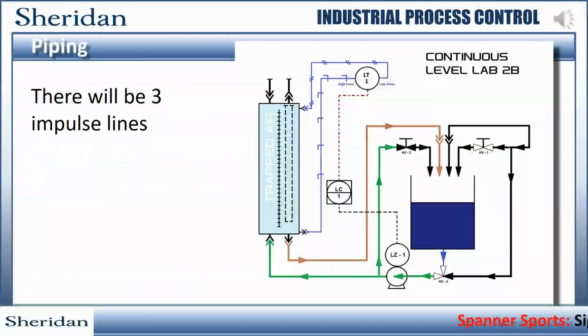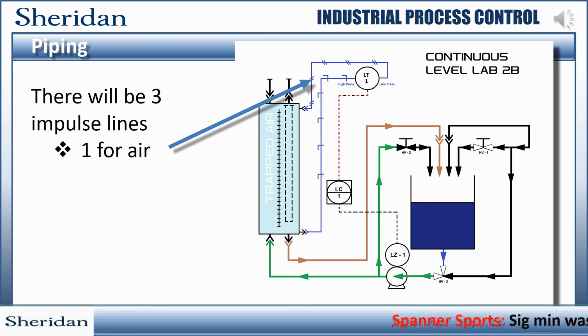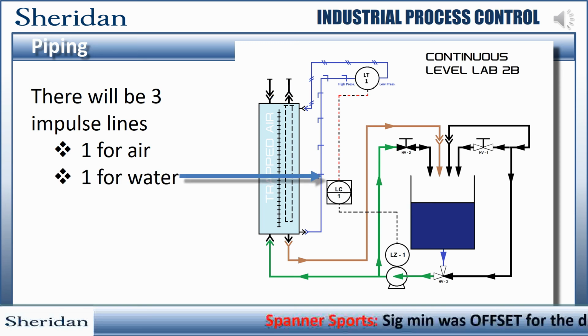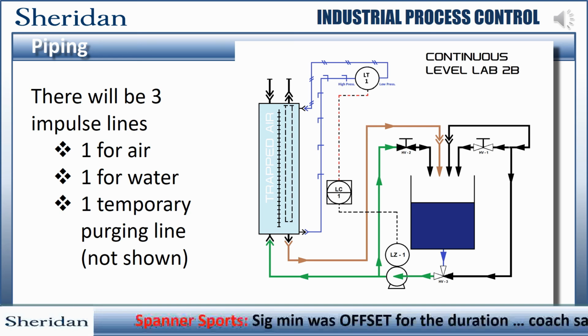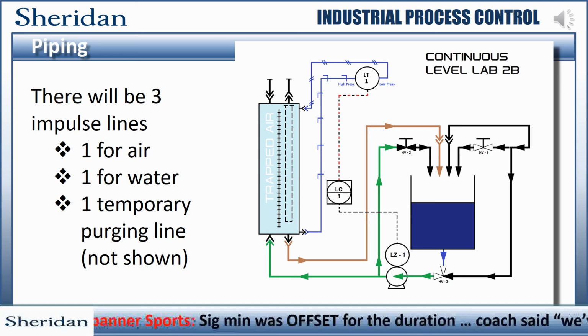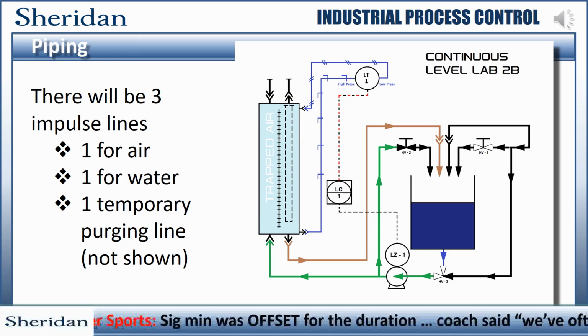You will need 3 impulse lines for this lab. One will be for the low pressure signal, which in this case will be provided by the trapped air above the control variable water in the receiver tank. Another will be used for the high pressure signal generated by the hydrostatic pressure of the water in the receiving tank. A third one will be used to purge or blow down the high and low pressure ports of the transmitter so that there is no unwanted fluids or debris in the transmitter to affect calibration.